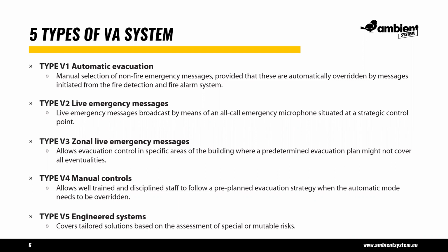They literally start with what's the automatic procedure for announcement, going through, well, we'd like to be able to give more emergency live messages from a dedicated staff member or fire officer in a strategic control place. Then you have zonal message systems where it's not necessarily clear cut what the evacuation strategy will be until the evacuation is required. And then through manual control, where again, more people are involved and they're actually using live messages to encourage people rather than pre-recorded.